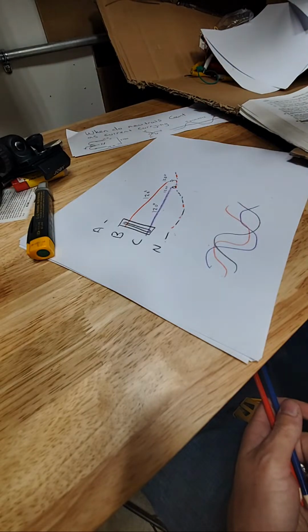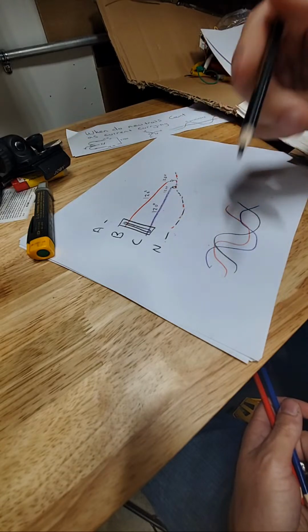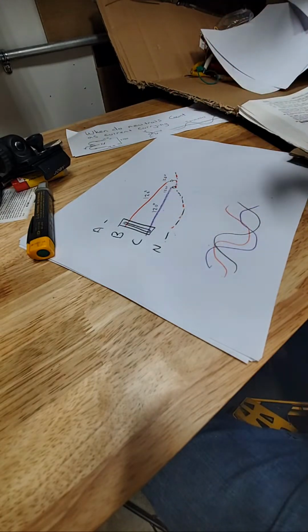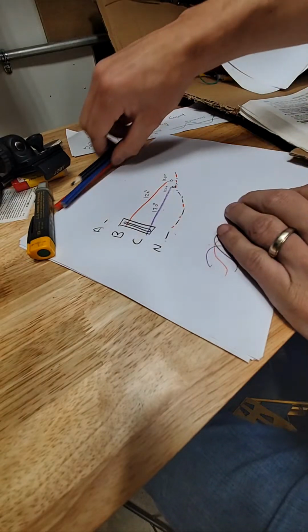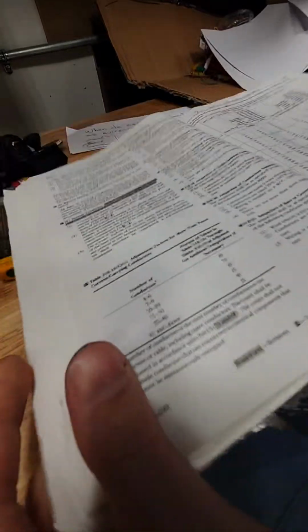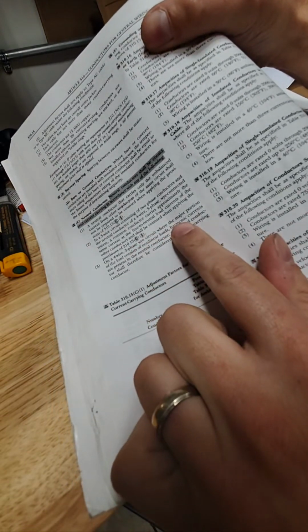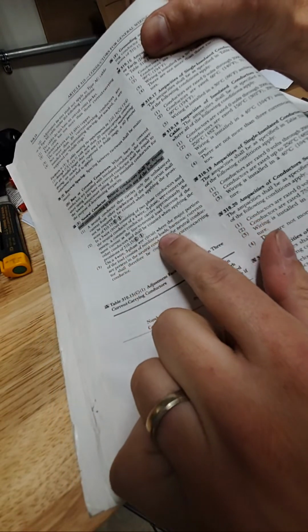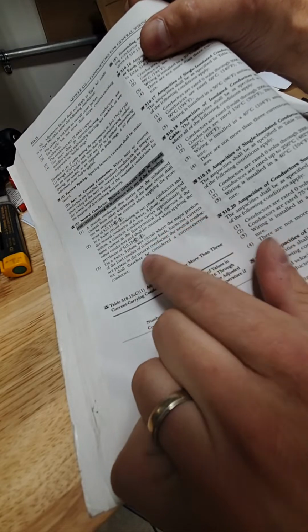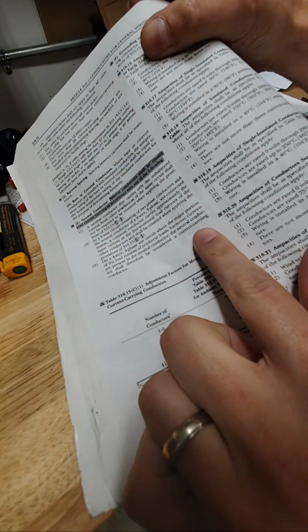Someone let me know, because when I did this in the field, man, I didn't share neutrals. You know, we ran a lot of nonlinear loads. I'm going to show you what a nonlinear load is, and then we're going to get out of here. Nonlinear load. On a 4-wire 3-phase Y circuit, where the major portion of the load consists of nonlinear loads, harmonic currents are present in the neutral conductor. The neutral conductor shall therefore be considered current carrying.